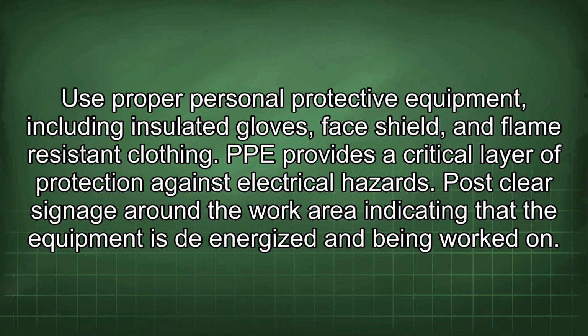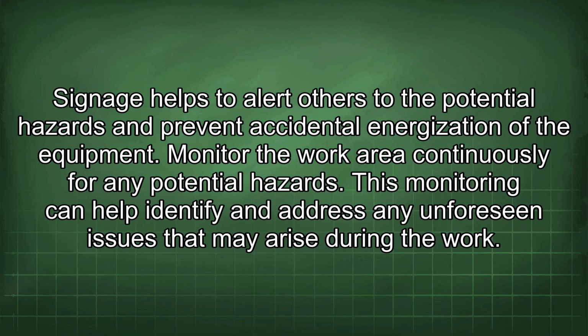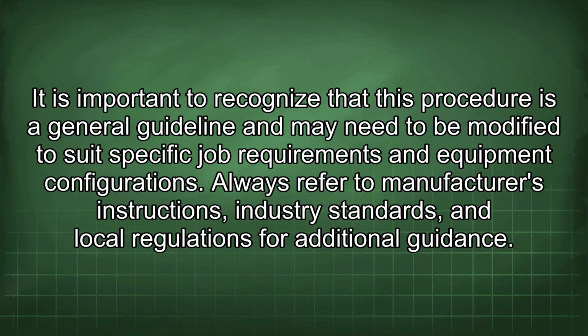Post clear signage around the work area indicating that the equipment is de-energized and being worked on. Signage helps to alert others to the potential hazards and prevent accidental energization of the equipment. Monitor the work area continuously for any potential hazards. This monitoring can help identify and address any unforeseen issues that may arise during the work. It is important to recognize that this procedure is a general guideline and may need to be modified to suit specific job requirements and equipment configurations. Always refer to manufacturer's instructions, industry standards, and local regulations for additional guidance.